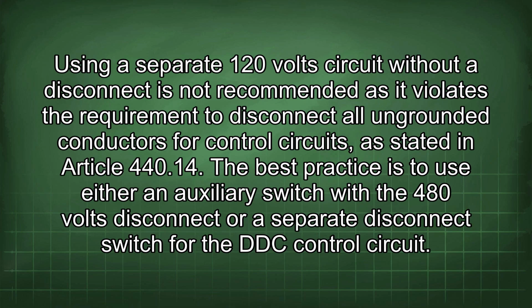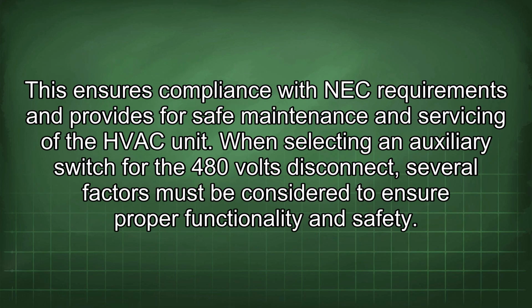Using a separate 120 volts circuit without a disconnect is not recommended as it violates the requirement to disconnect all ungrounded conductors for control circuits, as stated in Article 440.14. The best practice is to use either an auxiliary switch with the 480 volts disconnect or a separate disconnect switch for the DDC control circuit. This ensures compliance with NEC requirements and provides for safe maintenance and servicing of the HVAC unit.